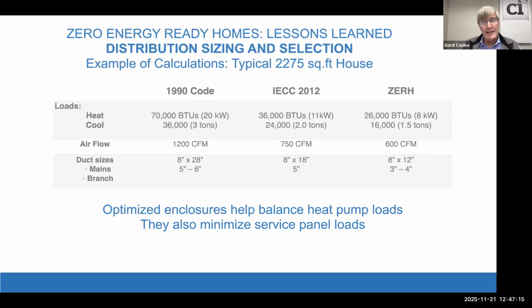That would be the equivalent of 20 kilowatts of electric heat. The air conditioning load would have been, well, we weren't air conditioning much back in the 90s, but 3 tons, 36,000 BTUs. Notice what happens as you get to even the 2012 code, or more importantly, the zero energy ready standard. We've cut those loads by basically 2/3. And more importantly, look how close together the heating and cooling loads are now. They're only 10,000 BTUs, less than a ton difference between the two.